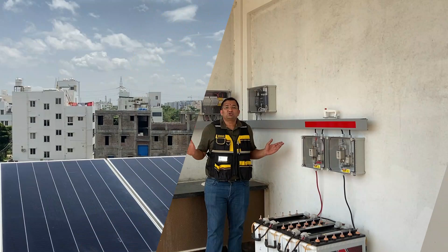In the DC wiring, we'll start with the solar panel wiring, that is the wiring from the solar panels to the charge controller. As shown earlier, we have 10 panels forming 5 strings, with 2 panels connected in series per string. This makes 5 fuses on the positive side and 5 fuses on the negative side.